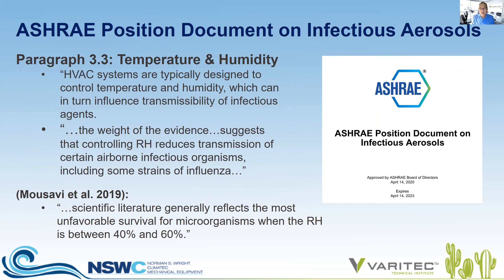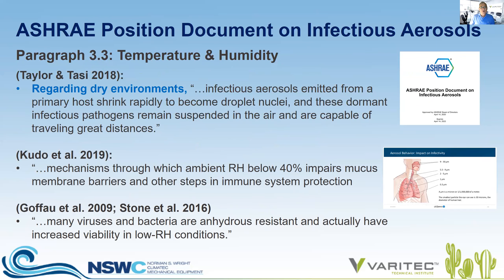Let's review some of the language from the ASHRAE position document on infectious aerosols, found on ASHRAE's Epidemic Task Force website. Referring to paragraph 3.3 on temperature and humidity, it states very clearly that the weight of evidence suggests that controlling RH reduces transmission of certain airborne infectious organisms, including some strains of influenza. The Mousavi et al. report for ASHRAE in 2019 states that scientific literature generally reflects the most unfavorable survival conditions for microorganisms when the RH is between 40% and 60%.